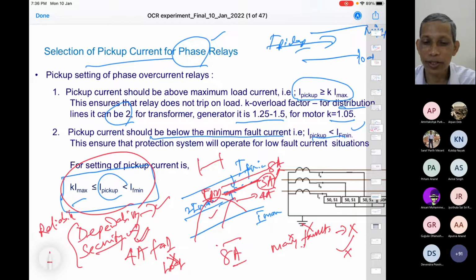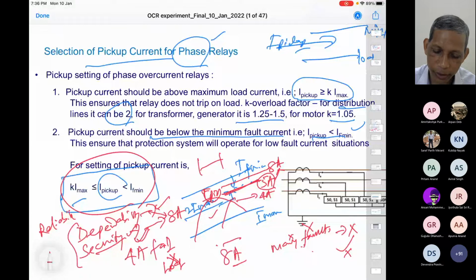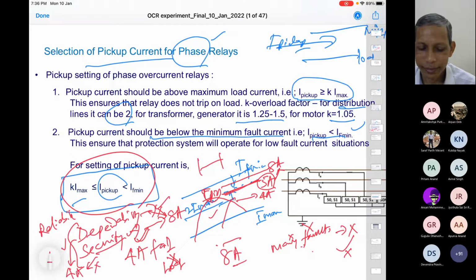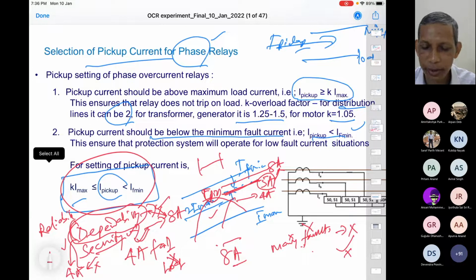So this asks for, you can say, better selectivity. Selective way. Which section is faulted? That section should be the only one isolated. So therefore, in this 4 ampere versus 8 ampere comparison, with 8 ampere, security is better, dependability is not better, poor. With 4 ampere, dependability is good, but security is not good. So for most systems, from the protection system perspective, what is required? Any fault, trip it. So we give higher emphasis to dependability. That is what the design philosophy happens to be.